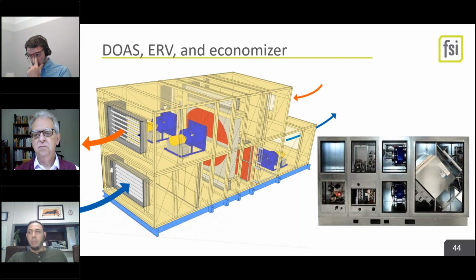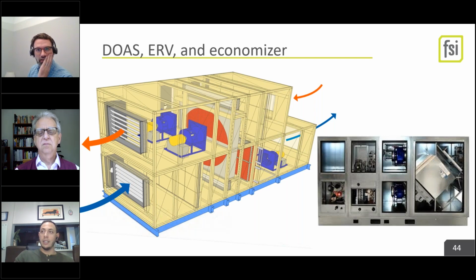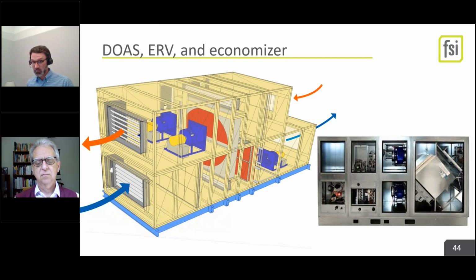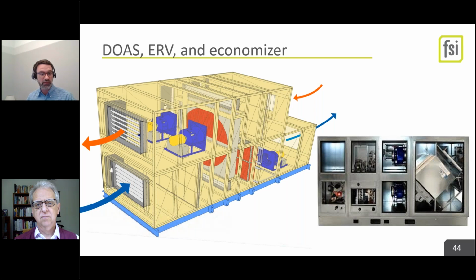So Ben, I had someone ask me for clarification on DOAS and economizers. Question being, when economizers are required for DOAS, do we really need to consider bypass requirement? And if not, could you explain exactly what an economizer requirement for a DOAS may mean? When we first saw this, they appeared to be conflicting, because when we think DOAS, we do not think economizer. So economizer is the ability to turn to 100% outside air.